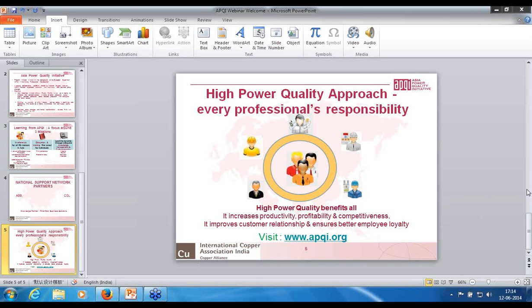And if you see, over a period of years, as my earlier presenter Dr. has covered, because of the recent more and more sophisticated power electronics, nonlinear loads are getting added to our domestic applications. So this is also producing lots of harmonics, and these harmonics finally result in the line. If we do not compensate at the low voltage side or maybe medium voltage side, they will often go upstream and create more problems, and havoc can happen like it has happened in other states and countries.